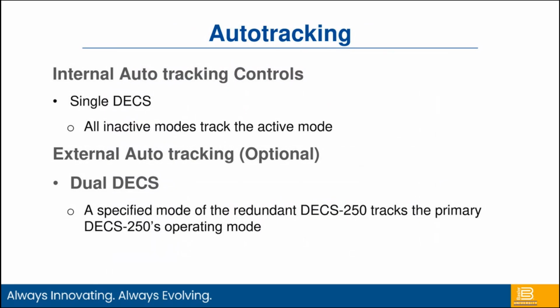Some of the other things we do in voltage control, with digital voltage controllers we're able to do redundant systems or redundant functions. We do this through auto-tracking. With a single DECS unit, we have internal auto-tracking controls. This allows the DECS to track mode to mode. So let's say I'm running in power factor mode. I can also have my VAR mode tracking, my AVR mode tracking, or my manual mode tracking. This is very useful, especially when I have a loss of sensing configuration and want to transfer to manual. It allows me to keep that machine online in manual and bring it down safely rather than tripping it off, maybe under load.